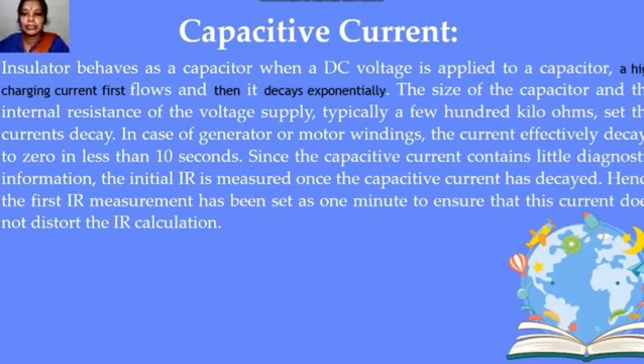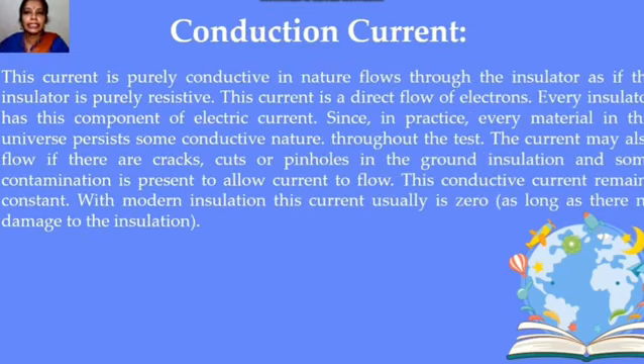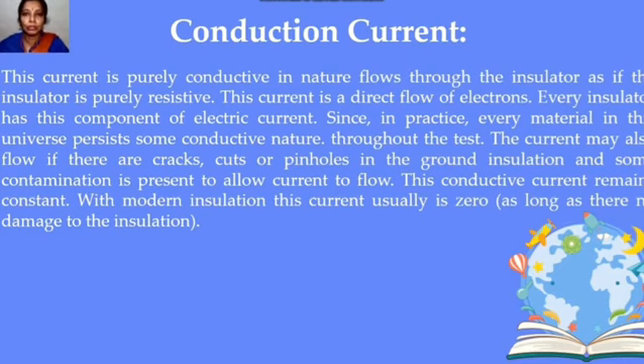Since capacitive currents contain little diagnostic information, the first IR measurement should be made at one minute to ensure this current has no contribution in the IR calculation. After 10 seconds the capacitive current becomes zero. The conduction current flows in the dielectric material; as it is highly resistive, this current is very low. This current may also flow if there are cracks, cuts, or pinholes in the insulation, or if certain contamination is present. This conducting current remains constant and does not vary with temperature and time.